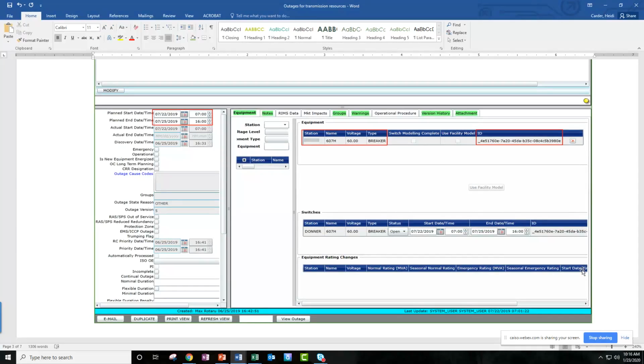Okay, so if there's SCADA telemetry that actually has a breaker closed, say let's use an example of a low side gen breaker, but the OMS has that switch modeled open, that modeled open outage information will supersede the telemetry. So you might go to your SCADA system, for example, and say, hey, I don't understand why this resource is being electrically disconnected. I show my SCADA as having that breaker closed, but there's probably an outage that's causing that disconnect, either at the low side or maybe at the substation level. So check the equipment, make sure that the switches are modeled correctly.